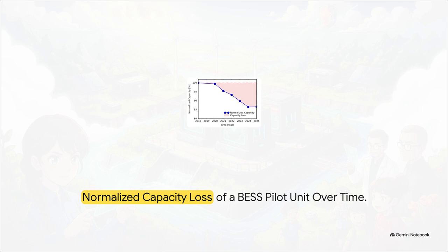As temperatures constantly fluctuate, the battery's degradation accelerates rapidly. Extreme heat speeds up unwanted side reactions inside the lithium-ion cells, while extreme cold limits charging and slashes usable capacity. The real kicker: uneven temperatures cause cells sitting right next to each other in the same module to age at completely different rates. That directly kills a project's long-term return on investment, forcing premature equipment replacements and crippling reliability right when the grid needs power the most.